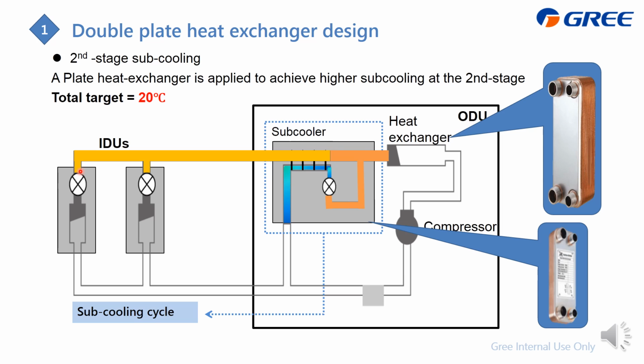Do you know why we need to set up this subcooler? Or what benefit we can get from the subcooler? Okay, the answer is that we can get a higher subcooling degree. On one hand, as you can see, the liquid coming out from this outdoor unit has a destination, which is the furthest indoor unit from the outdoor unit. The further it is, the more likely the refrigerant will become gas when it flows to this destination. If we cool it down more, we can ensure that when it gets to the furthest one, which is this one, it still remains liquid.